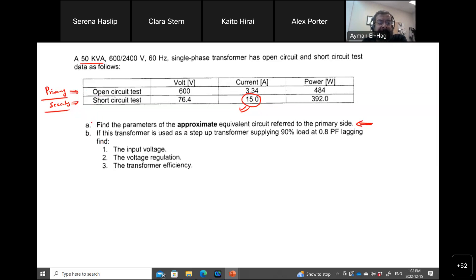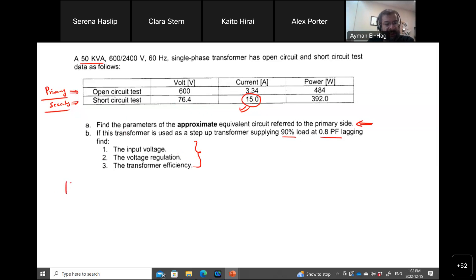So we need to find this. If the transformer is working at a certain condition — 90% of the load at a certain power factor — we need to calculate certain parameters. Let's start with finding the approximate equivalent circuit using the same formulas from the notes. We start by finding the value of Y, which is I_oc divided by V_oc, equal to 3.34 divided by 600.